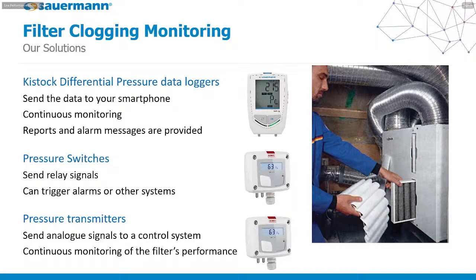A good way to indicate when a filter is starting to get very dirty and might need to be changed out is to look at the differential pressure, or the pressure drop, across any of the key filters in the system. And once again, you can set it up to give you an alarm. When you have a larger pressure drop, which is an indication the filter is very dirty and needs to be changed, you can get, through the software, an alarm or an indication that it's time to change the filter. So once again, it all ties back to IAQ, ensuring that you have high quality air in the room. Going back to what we talked about throughout the whole webinar so far, which is health, safety, and comfort, this is an example where you can use our stationary devices for that also.